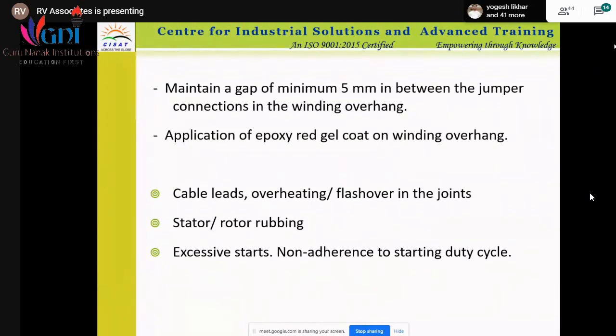First line, just see this: maintain a gap of minimum 5 mm between the jumper connections in the winding overhang. This gap should always be maintained everywhere. Just see the example, like a 3-pin. In a 3-pin, we have a distance between two terminals. That gap between the two terminals has to be maintained. If not, there will be a short circuit. Or if you don't want to say short circuit, it can be arcing. Arcing is not a short circuit. Current will flow, but it will give you a rise in temperature. The same thing happens with the motor terminals.